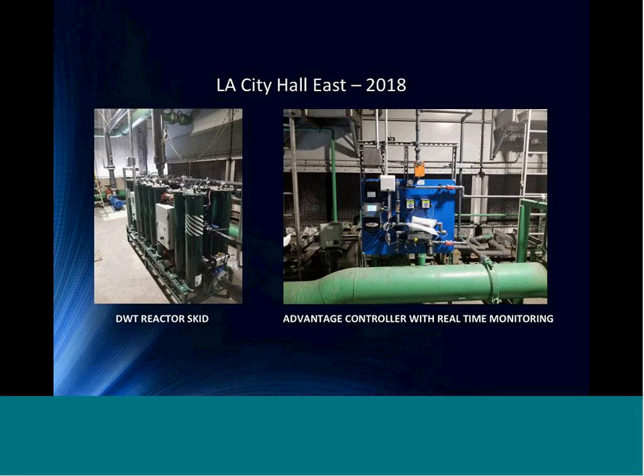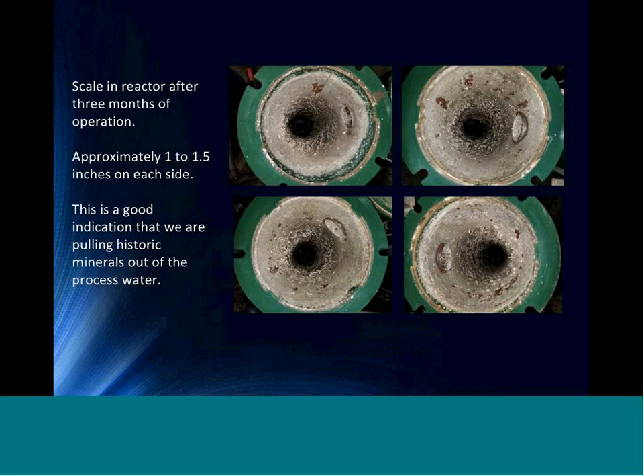In this image, you can see one of our reactor skids installed between 2 of the towers. And then, like Capture H2O, we use a real-time monitoring process where we get 24/7, 365 monitoring of all the particular parameters, the pH, ORP, conductivity, corrosion rates, so that we have active understanding of what the water chemistry is doing. We can also do a lot of predictivity, or basically predictions of how the water is trending. As we've seen the drought continue, we've seen quite a change in the water quality. Our system does react and adjust according to the resistivity of the water. So as conductivity varies, our reactor has a PLC controller that will change according to that modification of the water pH and conductivity. Next slide, please.